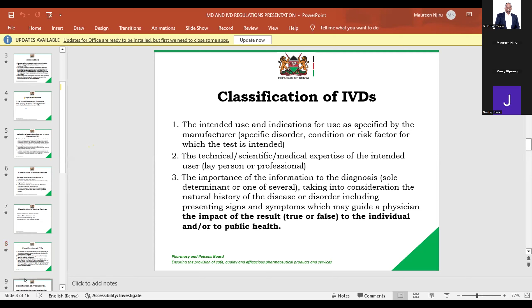Having said that, what are the classifications of in vitro diagnostics? We have class A. These are low individual risk and low public health risk. We have class B, moderate individual risk and or low public health risk. We go to class C, high individual risk or moderate public health risk, and class D, high individual risk and high public health risk. Unlike the medical devices where we just look at a risk-based classification, for the IVDs we look at the impact of the test to the individual health and the public health.